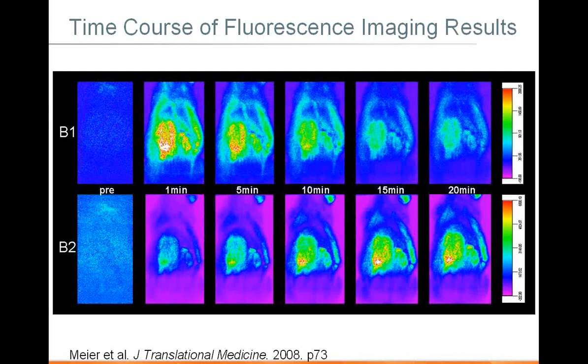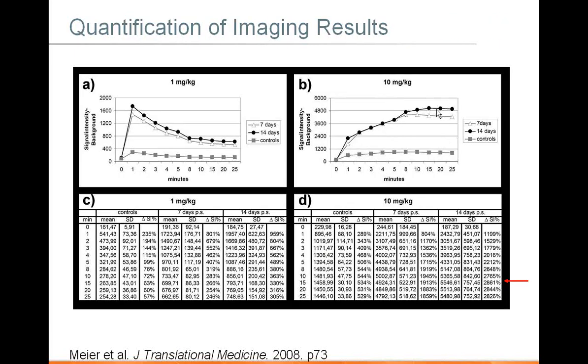As you can see just by looking at the fluorescence images, there are two different peak times for tracking the site of inflammation depending on the dose used. At the higher dose, the peak time is much later — 15 to 20 minutes into the study. That's not quite beneficial for researcher workflow because animal handling takes time: between injection, anesthesia with isoflurane, preparation, and placing the animal in the instrument, you want a buffer before your signal peaks. Additionally, working with the higher dose of ICG gives a much better signal-to-background ratio than the lower dose.